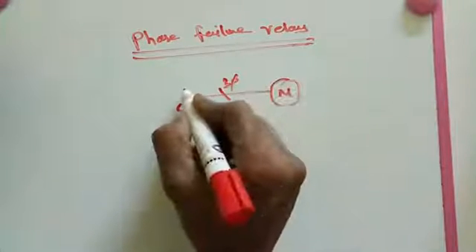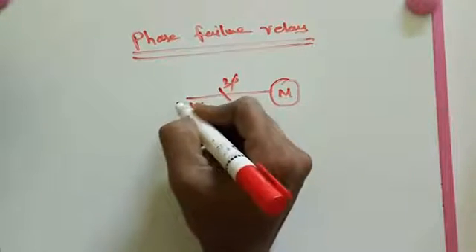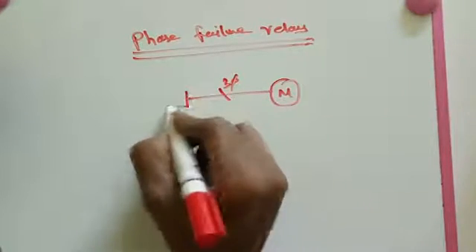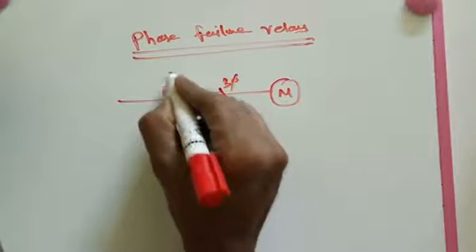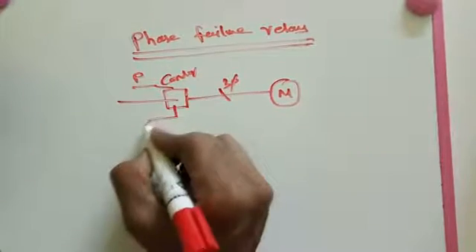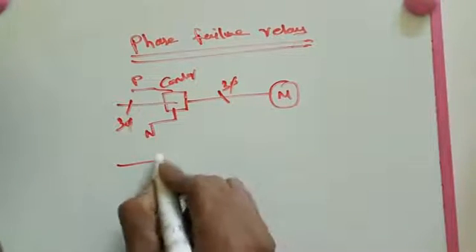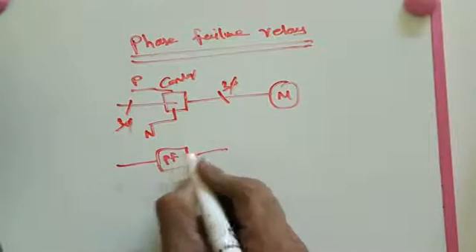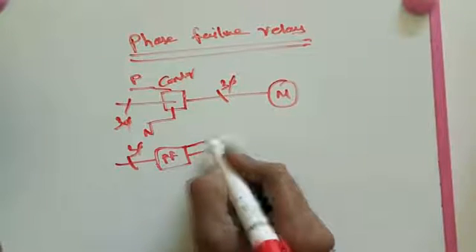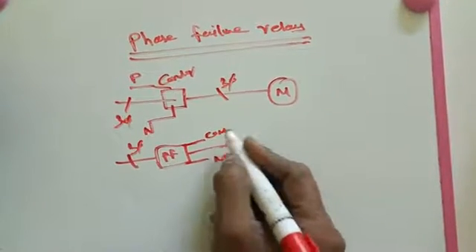That's why we make some control units — that is the phase failure relay. The three phase supply goes into the relay. The relay also needs a phase and neutral for auxiliary supply. The phase failure relay has three phase supply input terminals and control terminals: common, NO, and NC. This is how the phase failure relay terminals are arranged.